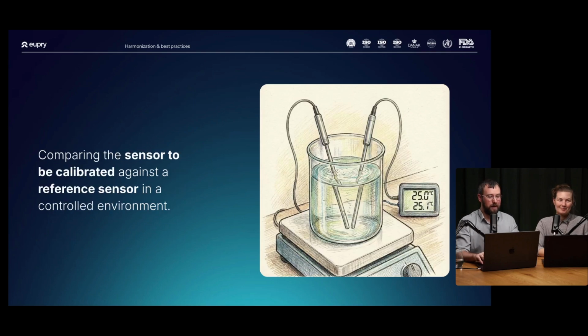So roughly speaking, what is a calibration actually? In practical terms, we compare a sensor to be calibrated, sometimes called the DUT, the device under test, or some call it DUC, device under calibration, against a reference sensor in a controlled environment. I don't think this would go for an accredited setup, but it explains nicely what we're talking about. The calibration laboratory would have a reference calibrated to a very high degree of accuracy and precision, and then use those measurements to compare with the device that we're actually trying to calibrate.